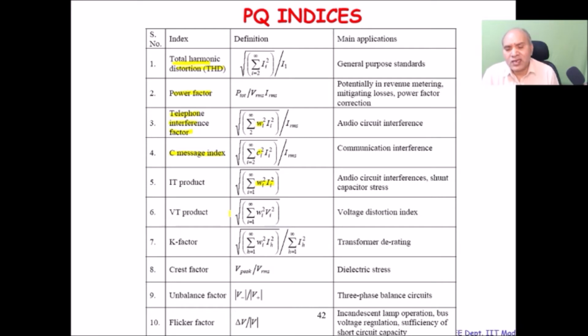There are some equivalent indices to get an idea about the effect of these quantities when we weight them through certain values like WI. So this is similar to the current, except now we are using voltage. Then the K factor for transformers is the ratio of the summation of WI squared IH squared, square root, over IH squared. Crest factor, unbalance factor, which I discussed earlier, and flicker factor, and so on. There are many figures of merit to indicate power quality. Nowadays they use wavelets to indicate the signature of voltages and currents, to indicate how they are and what their health is.